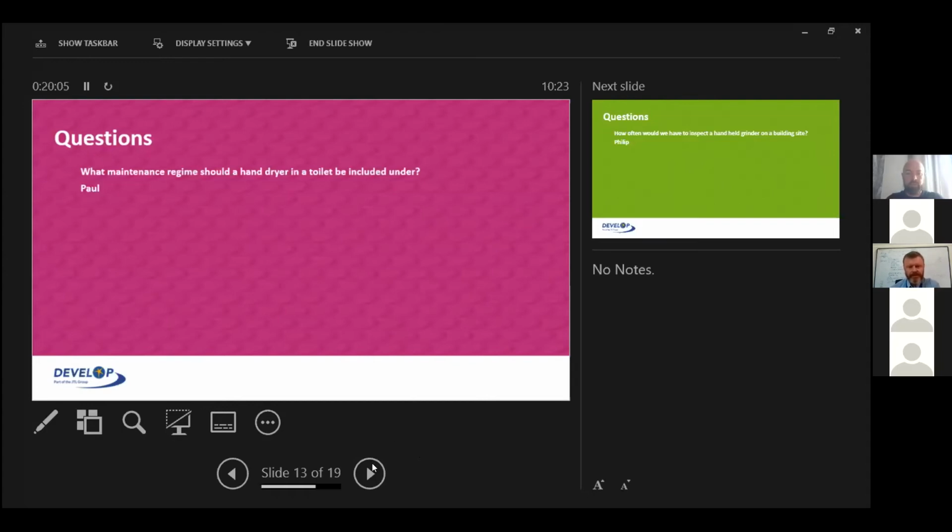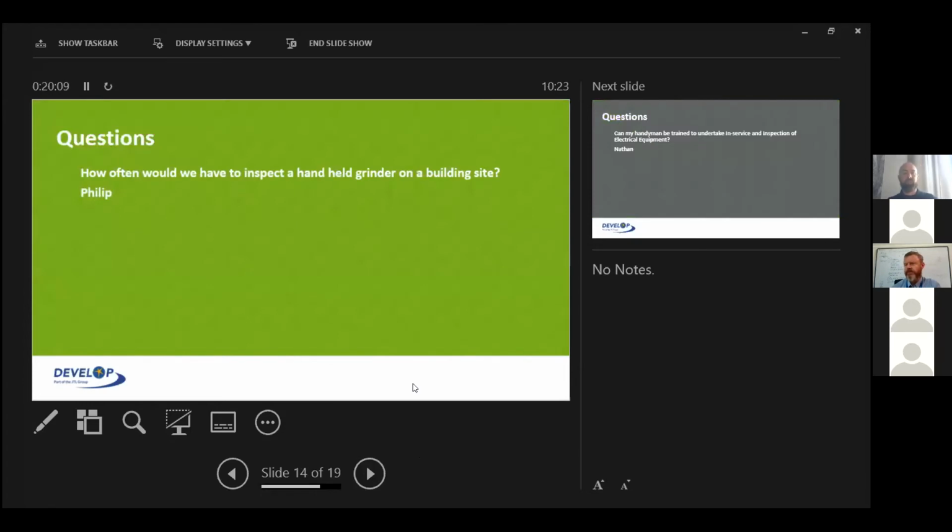Okay, thank you, Robbie. Let's move on to the next question that's come through. How often would we have to inspect a handheld grinder on a building site? The user should pretty much be doing it every time they use it. However, do your initial risk assessment and say, I will give it a formal visual inspection every 2 weeks, for example. So you've done it every 2 weeks for 3 months. Not a problem with it, not a fault on it. Okay, I'll extend it out. But again, it is based on your risk assessment. Is it being damaged? Is it being used properly? But be very careful with handheld equipment, especially if it's class 1 with a metal case, because they are the most dangerous pieces of equipment.